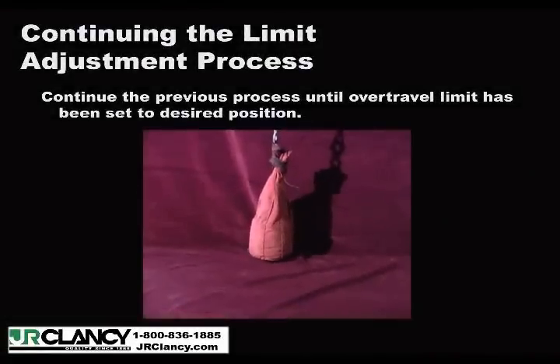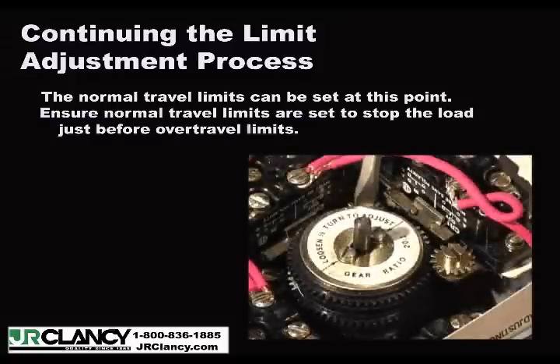Remember that it will take some time to get the limit adjusted properly. Now that the over travel limit has been set correctly, we can set the normal travel limit. Ensure that the normal travel limit is set to stop the load just before the over travel limit. To complete the limit adjustment process, drive the winch from one end of travel to the opposite end of travel. Remember that proper limit adjustment can take time.